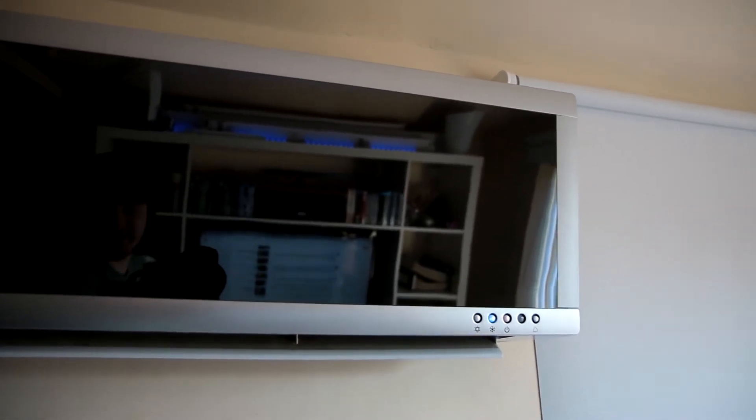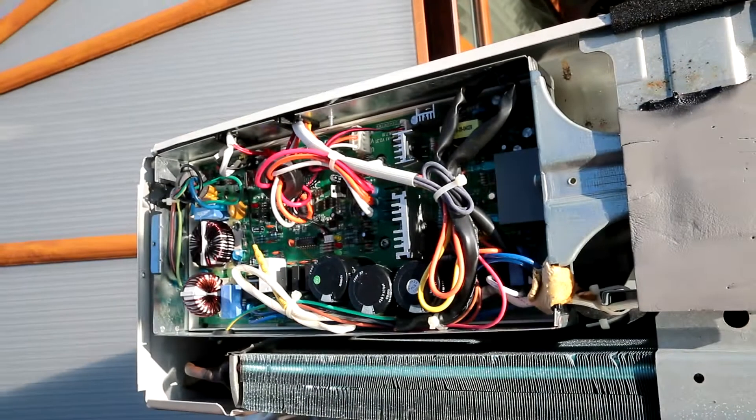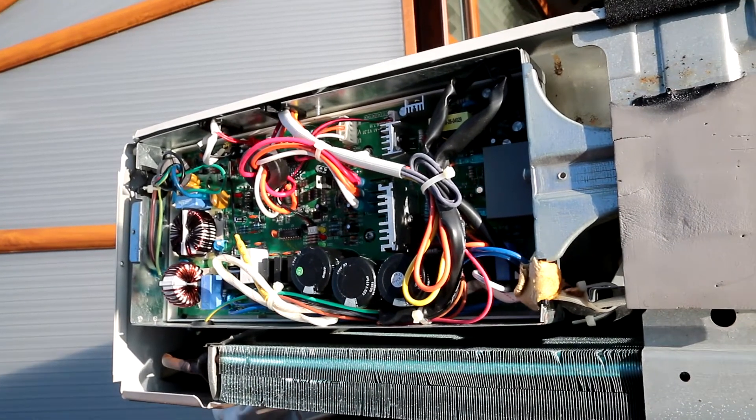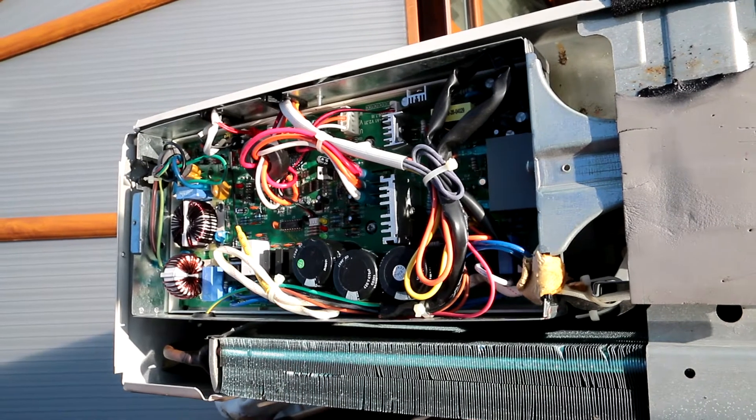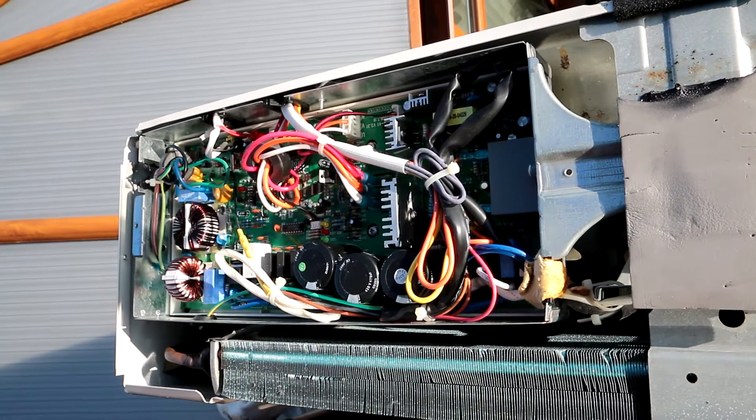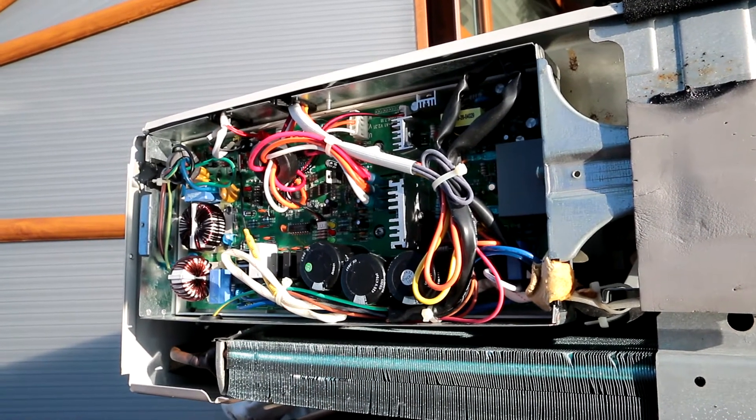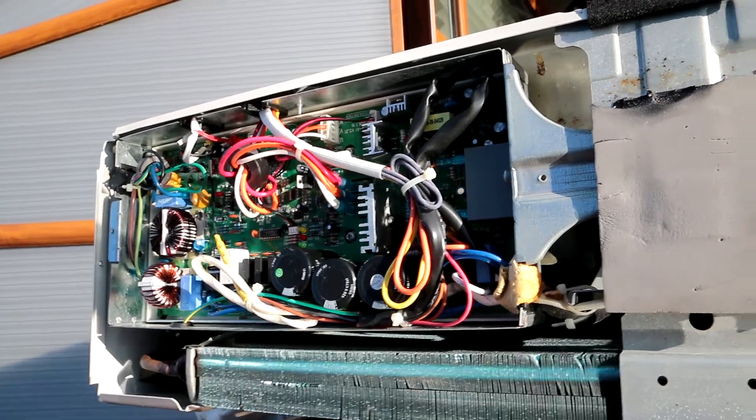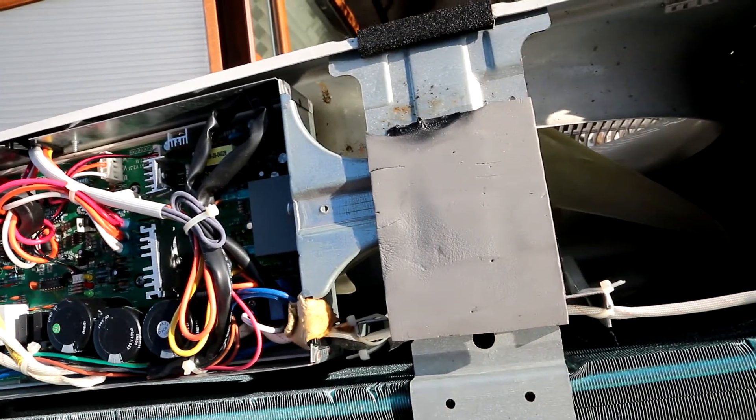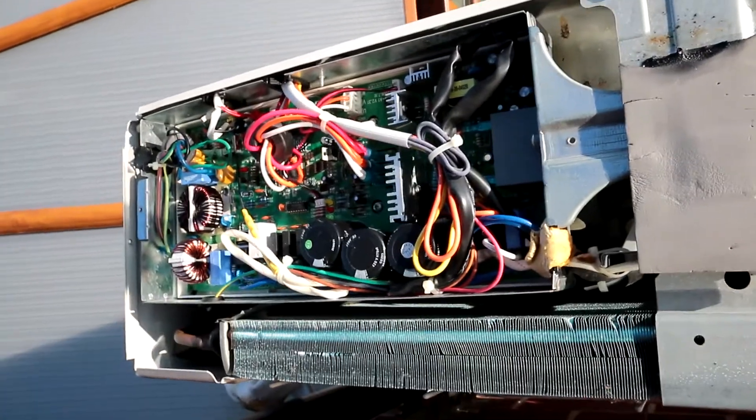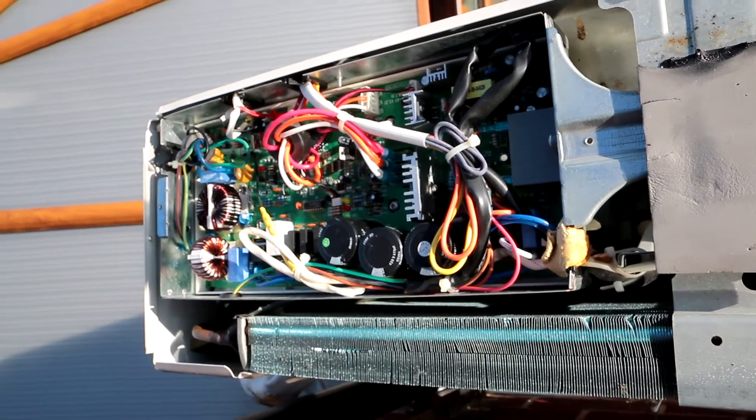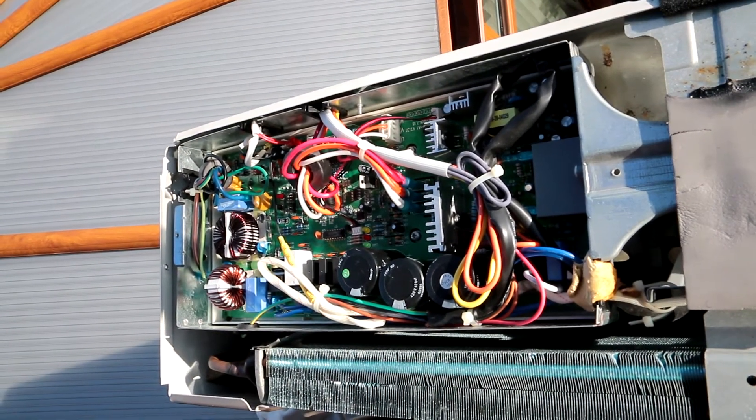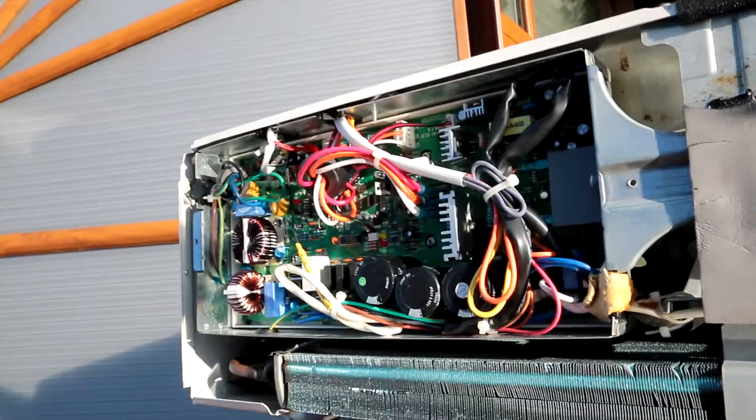The fault I'm getting is when I switch on to any cooling or heating mode, the indoor unit powers up fine, the fan comes on, the outdoor unit fan comes on, and you can sort of hear the compressor trying to start but it doesn't.